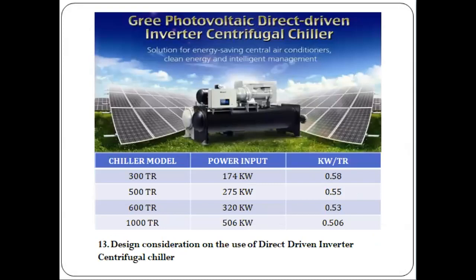Some bonus points. Design consideration on the use of direct-driven inverter centrifugal chiller. Designers, consultants, and developers can benefit from utilizing this GREE PV chiller, even if it is being used as a typical chiller for facilities without the connection of a photovoltaic system. Because of its high efficiency compressor, it ranges from the smallest chiller of 300 TR with kilowatt per ton of 0.58 up to 1,000 TR with kilowatt per ton of 0.506.